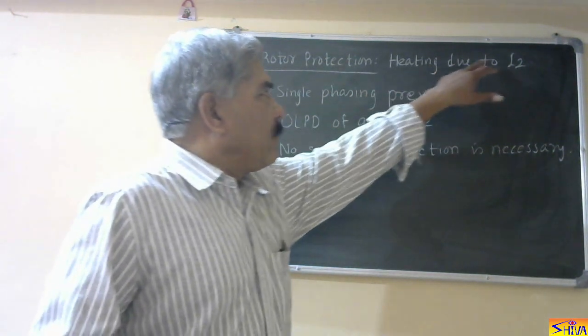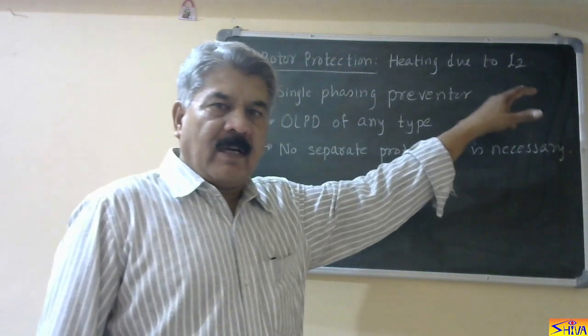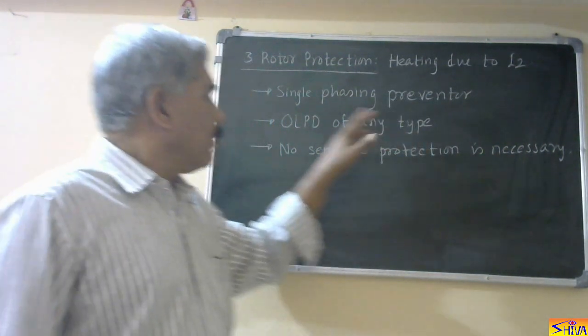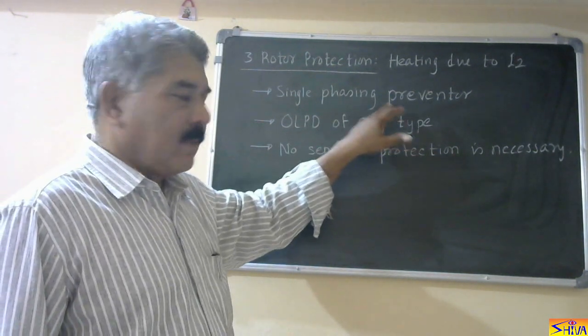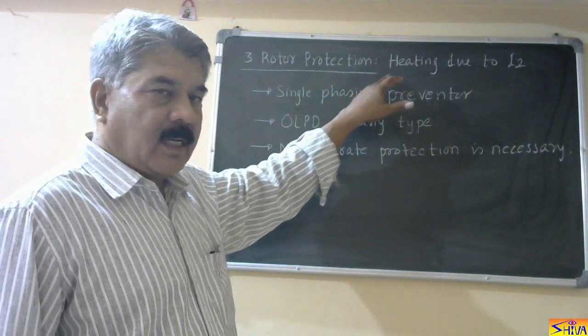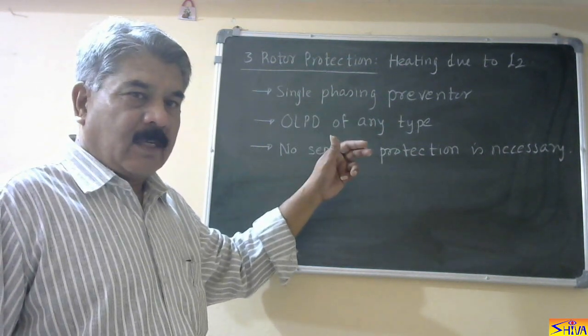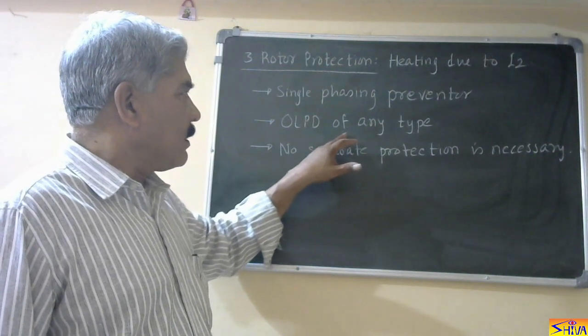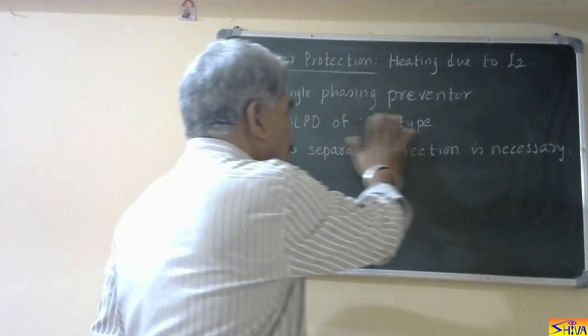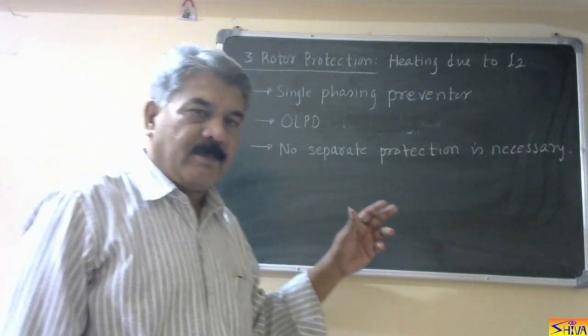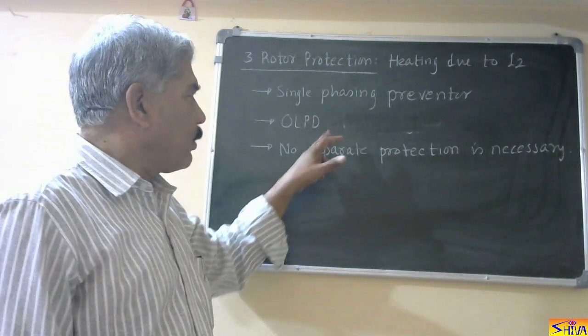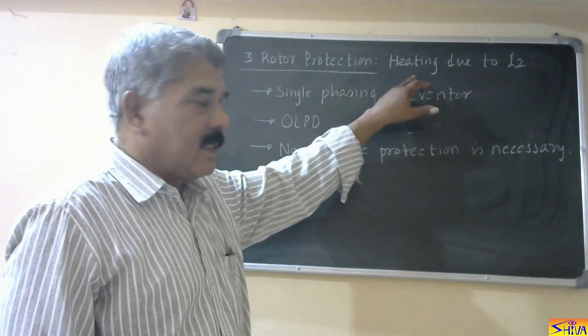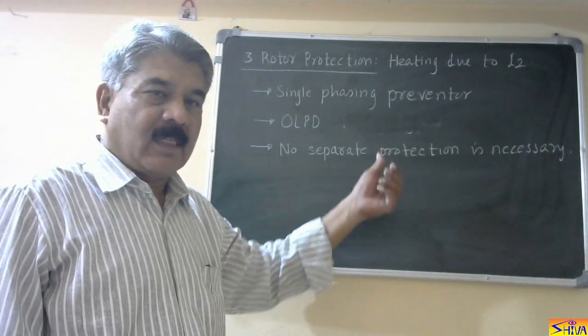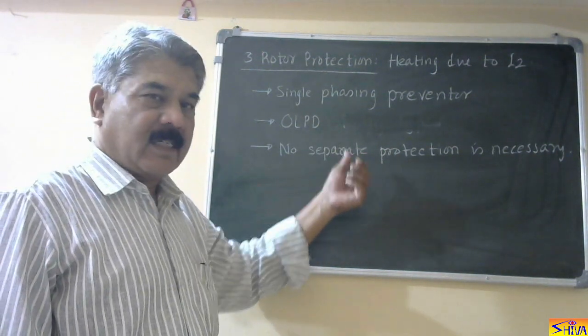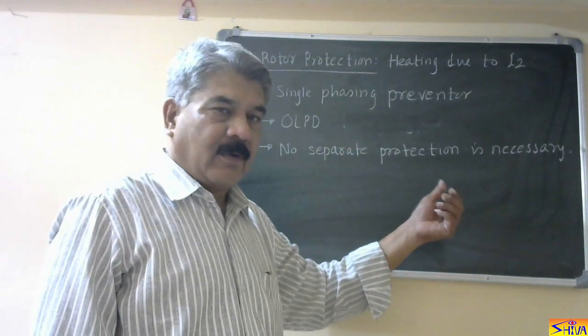So heating of the rotor is there due to the negative sequence component of the current, which is the result of unbalanced supply voltage or single phasing. The protection used for single phasing, that is the single phasing preventer, can protect the rotor against these conditions. Now this is causing heating of the rotor, so heating in general takes place. So an overload protective device, not of any type, sorry, but an overload protective device which has operation based on temperature, can protect the rotor against this condition. Because heating is there, this increases the temperature, and the temperature sensing overload protective device detects this condition. So no separate protection is necessary for the rotor.